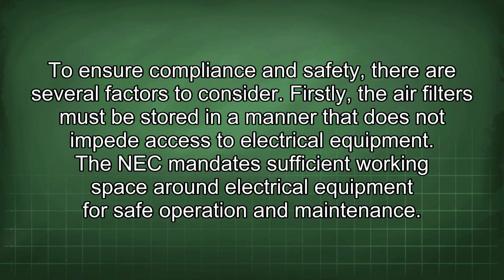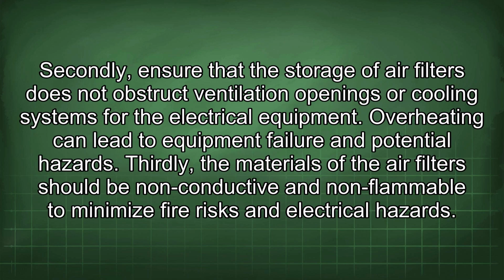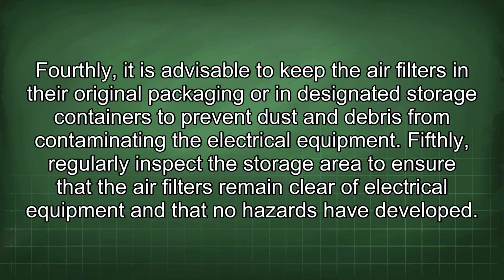Firstly, the air filters must be stored in a manner that does not impede access to electrical equipment. The NEC mandates sufficient working space around electrical equipment for safe operation and maintenance. Secondly, ensure that the storage of air filters does not obstruct ventilation openings or cooling systems for the electrical equipment. Overheating can lead to equipment failure and potential hazards. Thirdly, the materials of the air filters should be non-conductive and non-flammable to minimize fire risks and electrical hazards. Fourthly, it is advisable to keep the air filters in their original packaging or in designated storage containers to prevent dust and debris from contaminating the electrical equipment.